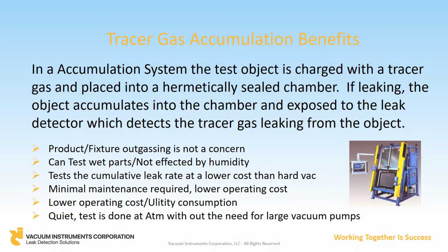The next few slides will offer an explanation of the features and benefits for the various testing approaches. As the name implies, helium accumulation involves placing the object under test in a hermetic enclosure, or what is sometimes referred to as a clamshell. The object is then evacuated and backfilled with helium to a preset pressure. After a period of time, the chamber or clamshell is sampled using a helium sniffer to detect the presence of any helium tracer gas that has leaked out during the accumulation phase of the test.